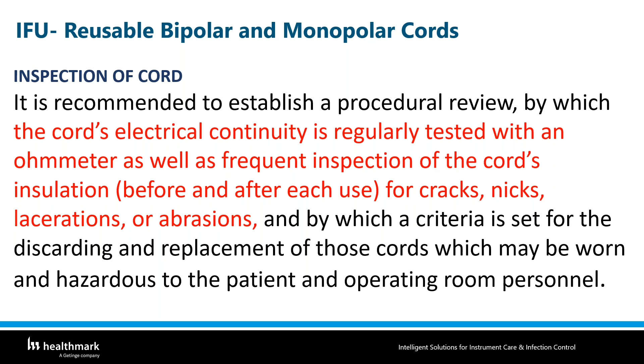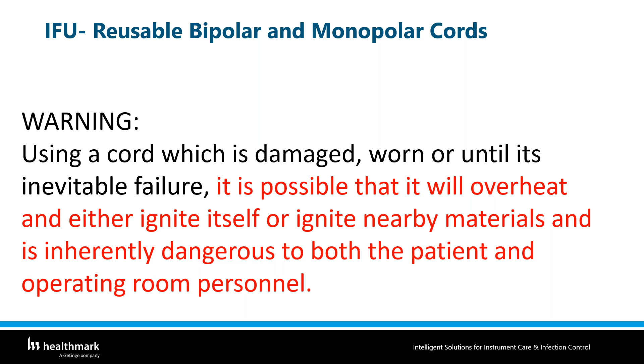Unlike the shavers and endoscope, the IFU on this cord says that the cord's electrical continuity needs to be regularly tested with an ohm meter, as well as frequent inspection of the cord insulation. So the IFU says you need to look at that, but we know that there are not many ohm meters in the SPD department. So here again on that warning, it is possible that it will overheat and either ignite itself or ignite nearby material, and is inherently dangerous to both the patient and the operating room personnel. So these are basically right off the monopolar and bipolar cords IFU.